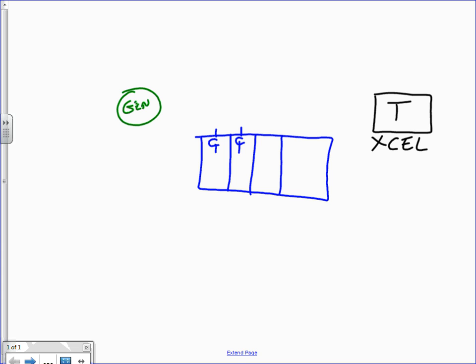That's my pad mount transformer from Xcel. So I'm bringing my, whatever this works out to be, it should be a significant feed from my transformer into my main gear. And then my genset, I'm bringing into my main gear. And these main breakers would be electrically controlled, and such that, kind of oversimplifying, they feed all of the big loads that come out of this main gear.